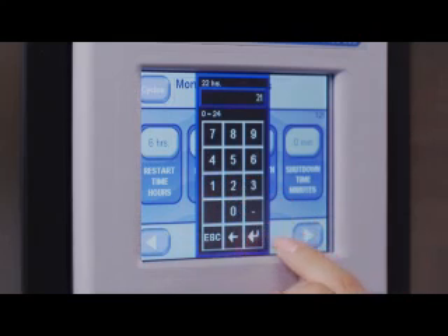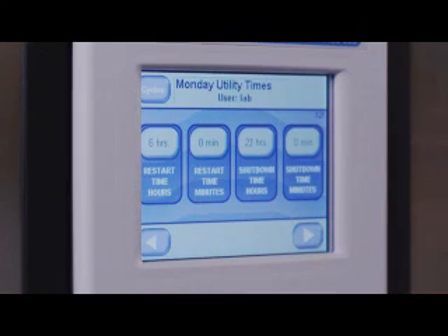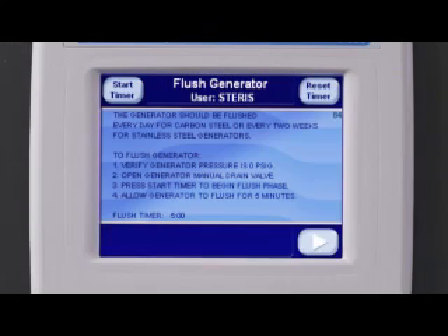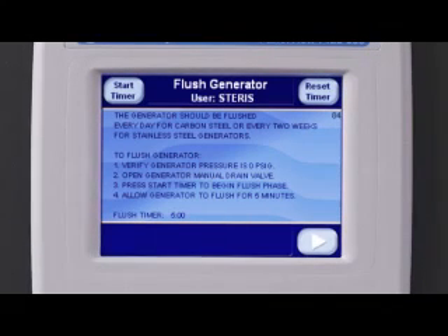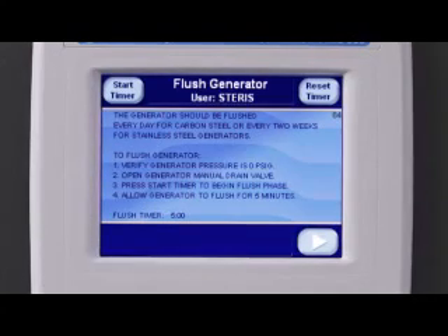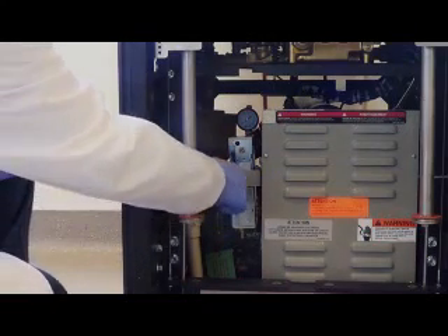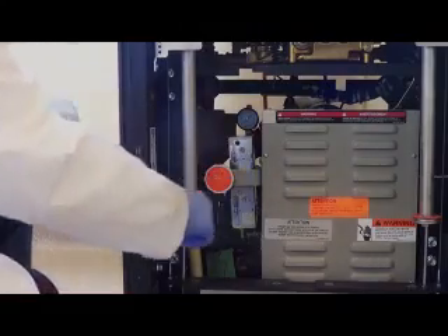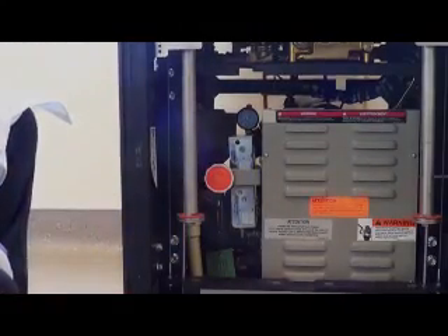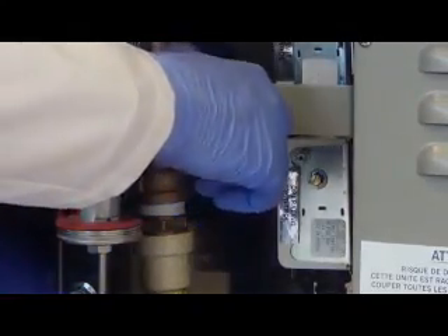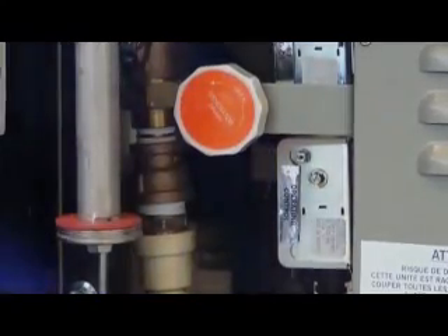For those sterilizers that are not equipped with an automatic flush, there's a simple procedure for flushing the generator manually. Upon starting the sterilizer in the morning, the initial screen will prompt the user to flush the generator and provide a step-by-step guide. Follow the steps on the screen, beginning with verifying the steam pressure in the generator is 0 psig. Open the valve for the steam generator and press Start on the timer. Once the 5-minute flush is complete, the drain valve should be closed and the sterilizer is ready for use.